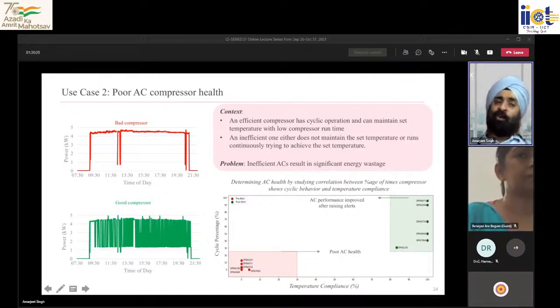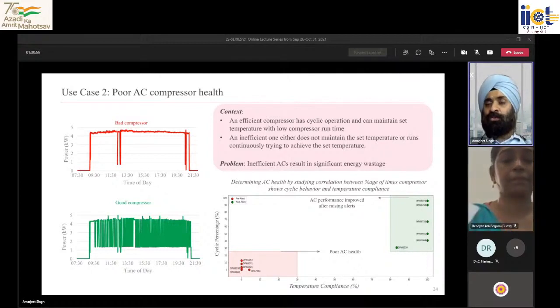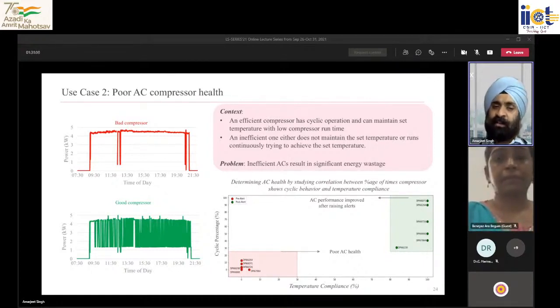If your compressor is on throughout the day, one, it is consuming more energy. Two, it's an indicator that the compressor will eventually have some fault and is going to break down. So it's also an indicator that it's time to get maintenance done, which leads to better management of your assets and reduced energy consumption, because if the compressor was on all the time, it's consuming much more energy.